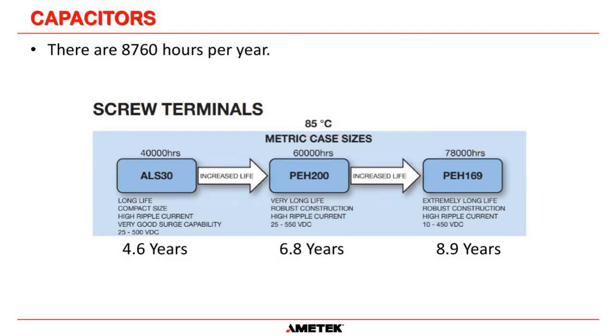Our design engineers worked out for the special capacitors that we use, at the temperatures that we operate our UPSs at, and the worst case scenario for those, I think, is 105 degrees Fahrenheit. Then we know our DC capacitors will give us 10 years of life. And that is why we replace them every 10 years. We know that our capacitors will last 10 years based on all the information that we have at hand.